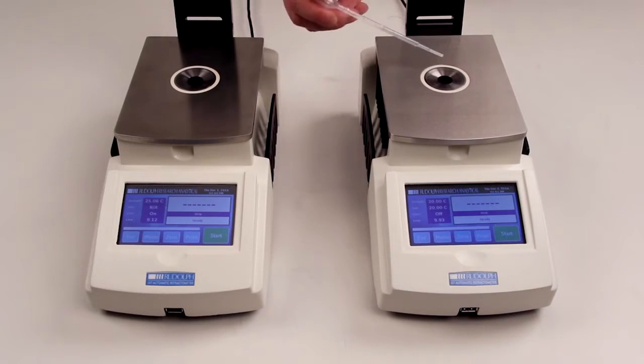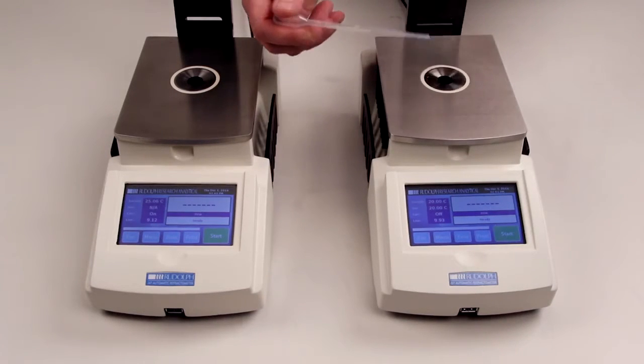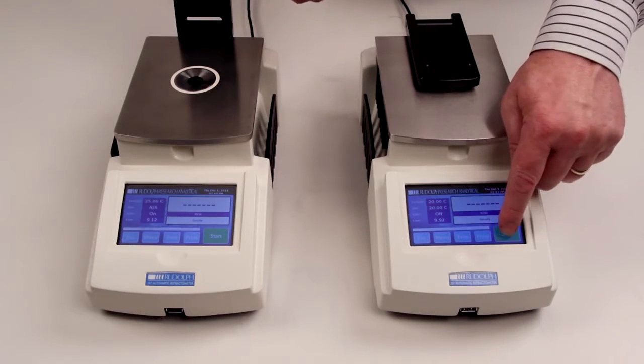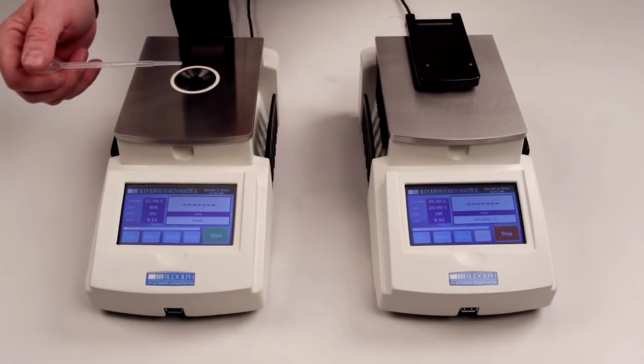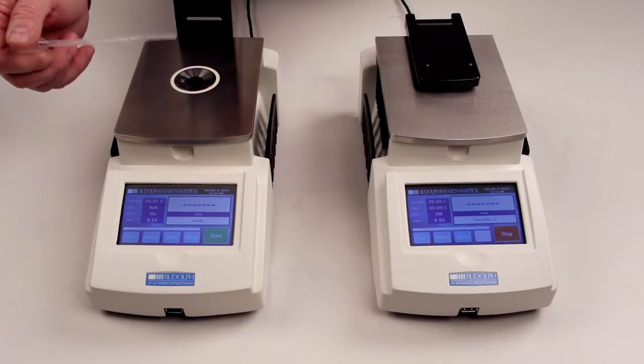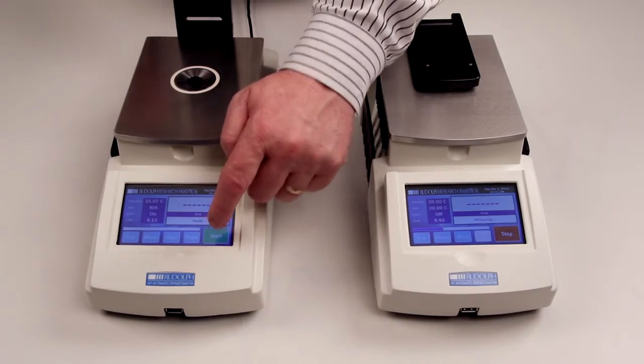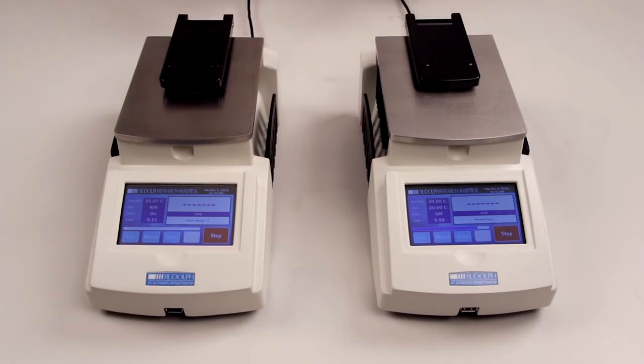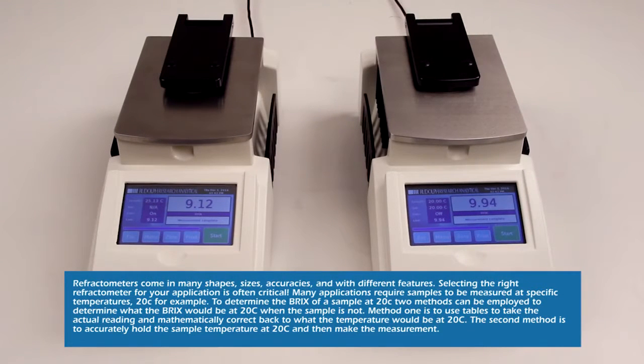If we place the calibration standard on both refractometers, they should, in theory, measure the exact same results. What we find is the temperature-controlled refractometer measures the calibration standard almost perfectly. The temperature-corrected refractometer, however, cannot measure the calibration standard since temperature correction will not work on a sample or standard that is not primarily sugar and water. We've just seen exactly why even a refractometer that measures primarily sugar and water-based samples will still need to be temperature-controlled. The issue becomes traceability.